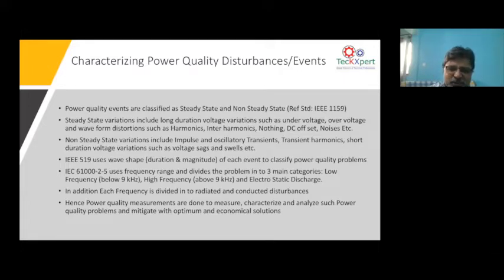But non-steady states are those which are not available all throughout the waveform. You will only see them come and go like a transient. It just comes and just goes away. A voltage spike just comes and goes away. So those are all classified as non-steady state power quality problems. And harmonics and under voltage, over voltage are all classified as steady state power quality problems. Now everybody must be familiar with IEEE 519, because when you look into harmonics, that's the common standard followed by everybody. But what IEEE does is it just looks at the wave shape of the waveform and tries to see the duration of that distortion and the magnitude of the distortion. So IEEE 1159 talks about power quality in total, steady state and non-steady state, but IEEE 519 talks specifically about waveform distortions.